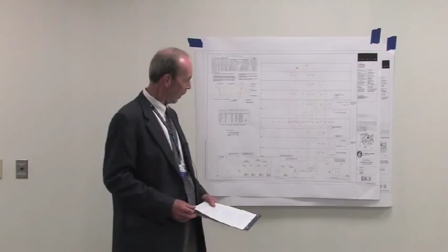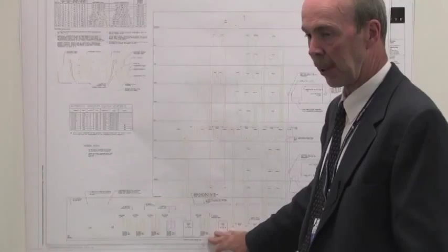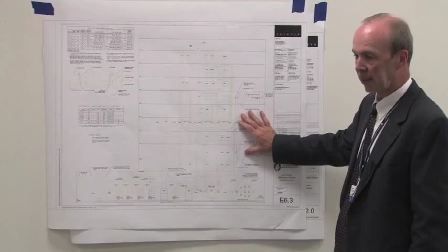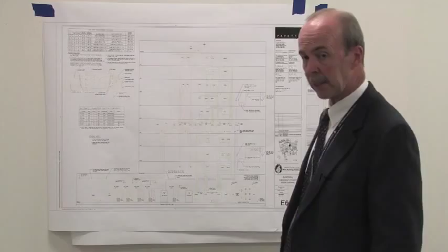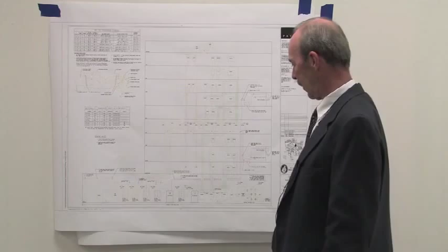What about equipment? Is the equipment riser... there's equipment here, Mike. There's equipment on the penthouse, equipment on level 4, and equipment down in the basement level. Basically, we put it exactly where you had it. There's also an imaging riser, dedicated to the imaging equipment only. Is that imaging riser 440? Yeah. That's what's backed by the flywheel, correct, imaging and critical have the flywheel backup. And what about an elevator riser? You got an elevator riser going? Put it on equipment, it's all part of equipment, so couldn't really justify putting in an elevator switch just for... I know, just asking. Yeah, no.